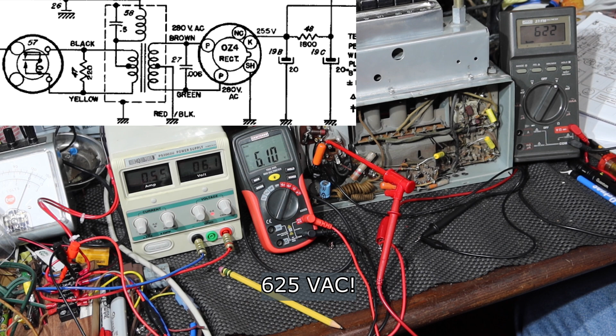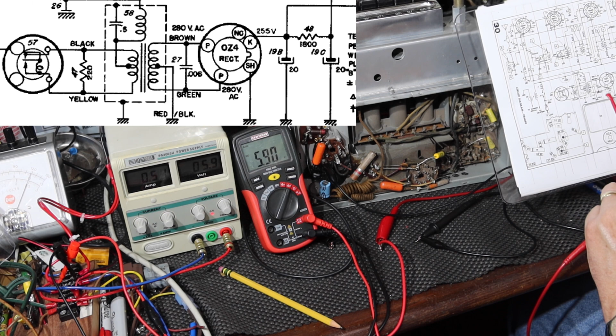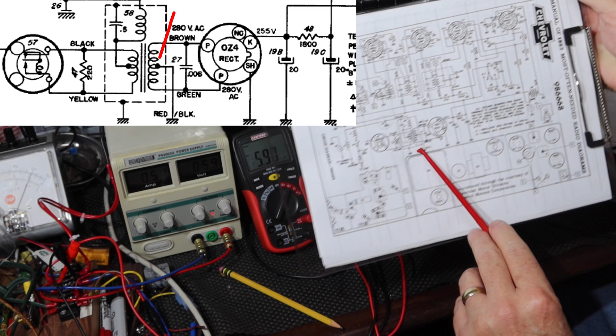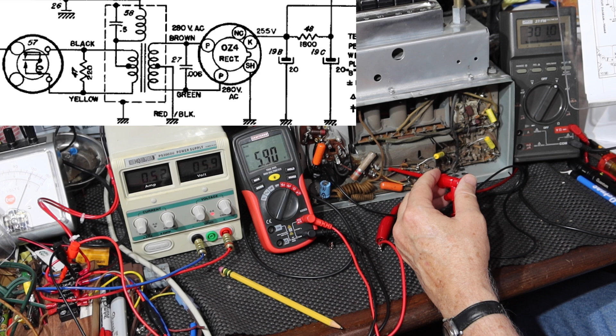Let's see, do we want to check both sides of the winding? We could probably do that if we wanted to. And from that plate, go to ground, right? If I go from one of these plates to ground, that'll be checking the center tap. So let's see what happens. 300 volts, they're supposed to be 280 or 290. I can't quite read what that says, but I think that's pretty good.